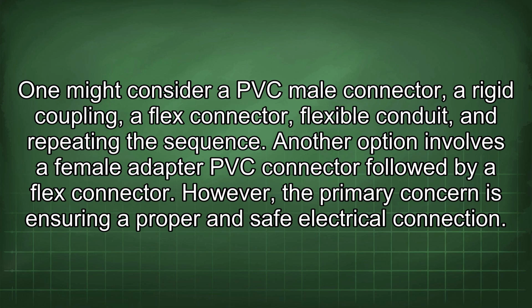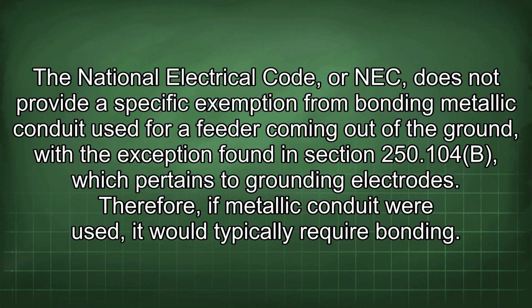However, the primary concern is ensuring a proper and safe electrical connection. The National Electrical Code, or NEC, does not provide a specific exemption from bonding metallic conduit used for a feeder coming out of the ground, with the exception found in Section 250.104(B), which pertains to grounding electrodes. Therefore, if metallic conduit were used, it would typically require bonding.